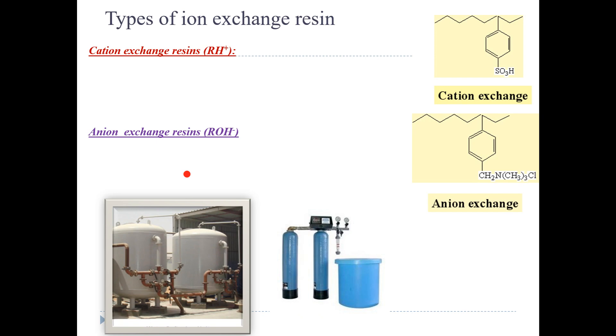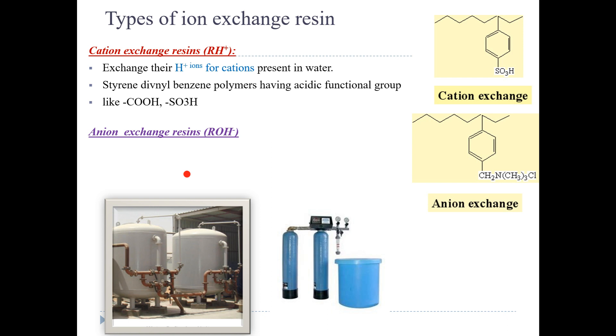The advantage of ion exchange resin is that you can get rid of both cations and anions. There are two exchangers: cation exchanger and anion exchanger. In the cation exchanger, the polymer has H+ ions which can be replaced — they exchange H+ ions for cations. Styrene divinylbenzene polymers have acidic functional groups such as –COOH or sulfonic acid group. For example, H+ is replaced by Ca2+.